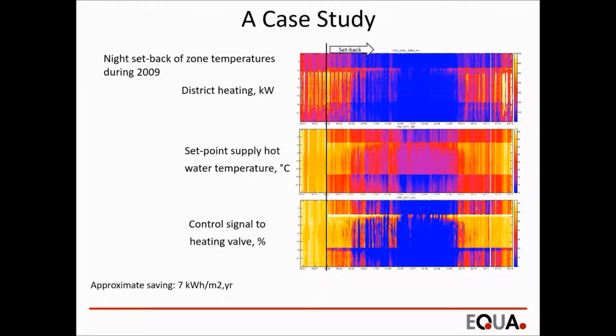So here are some carpet plots showing the district heating, the set point of supply hot water temperature, and the control signal to the heating valve. And what you see here is on the y-axis the time of the day, and on the x-axis the time of the year, and then we color code the variable. Actually, you don't see the scale very well, I think, but it doesn't matter. You can see the pattern there, and that's enough. So the first month, January, we didn't have any setback, and then you can see, for example, that the set point of the supply hot water temperature is varying slightly, and that's because it's a function of the outdoor air temperature, as is common.